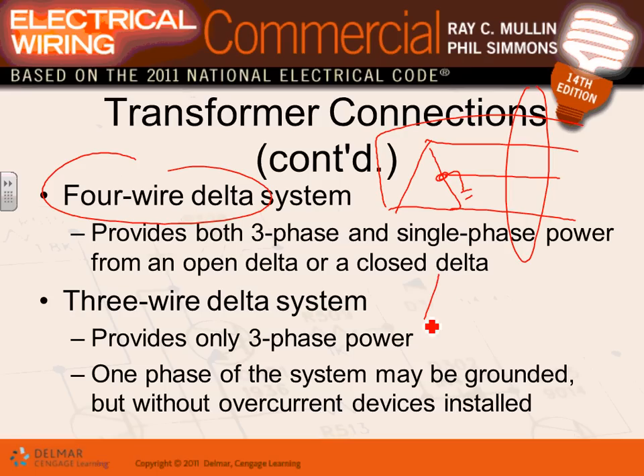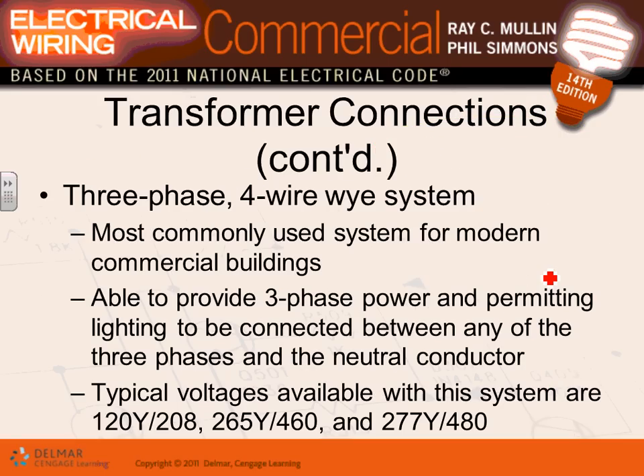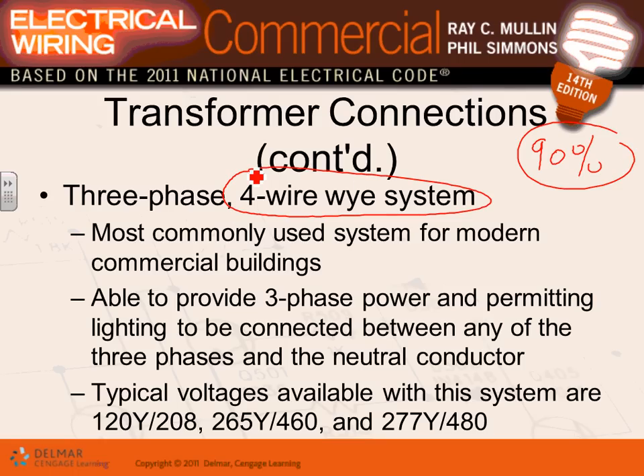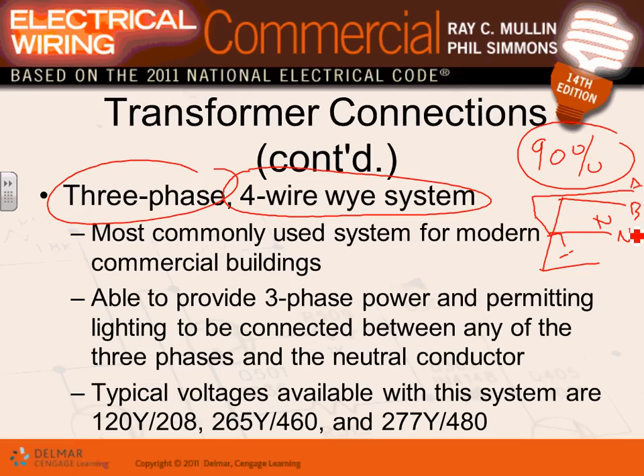Three-wire delta, when you only have a delta like this, can only feed your three-phase loads. You don't have anything to feed single-phase loads. The most important one, which you will live with in almost 90% of the systems you're going to encounter, is called three-phase four-wire Y. These are a Y like this, and here's all the phases, and here's the neutral coming out of here. And here's your phase A, phase B, neutral, we talked about it here, and we have C.